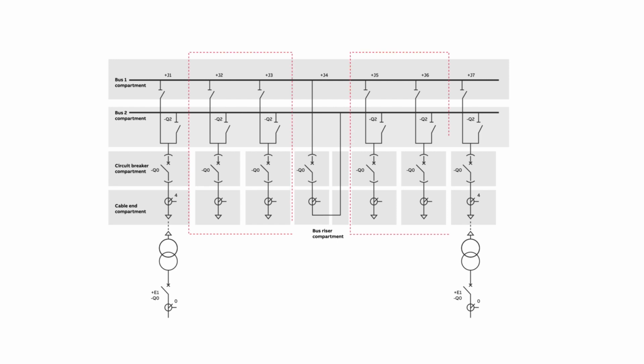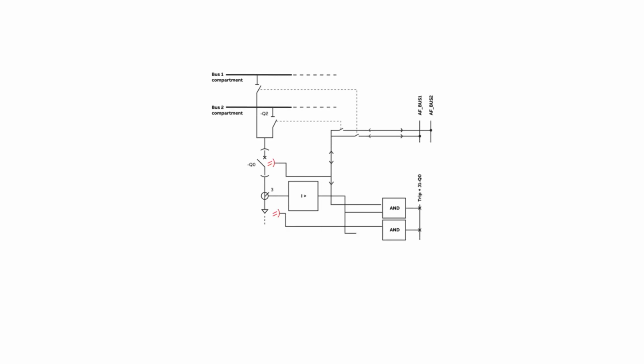Next, Matthew has to consider the feeder bays with a similar approach. Depending on where the arc fault is, in the circuit breaker, in the cable compartment, or in the bus bar, the selectivity logic needs to be prepared differently. To accomplish this, there needs to be 2 arc light sensors connected to the protection relays, and the relays also need the current measurement from their own bays.